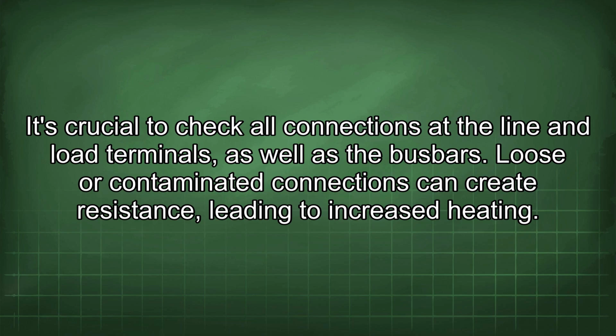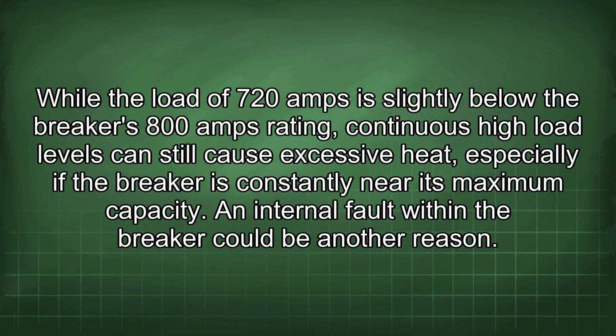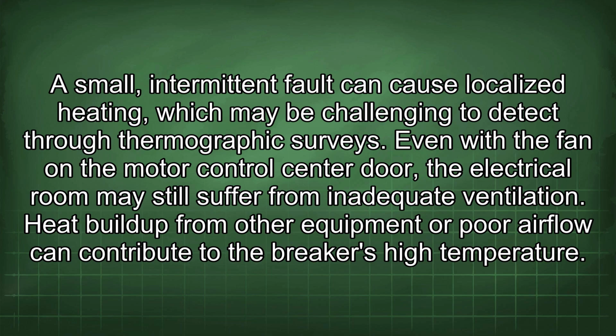It's crucial to check all connections at the line and load terminals as well as the bus bars. Loose or contaminated connections can create resistance, leading to increased heating. While the load of 720 amps is slightly below the breaker's 800 amp rating, continuous high load levels can still cause excessive heat, especially if the breaker is constantly near its maximum capacity. An internal fault within the breaker could be another reason. A small, intermittent fault can cause localized heating, which may be challenging to detect through thermographic surveys.